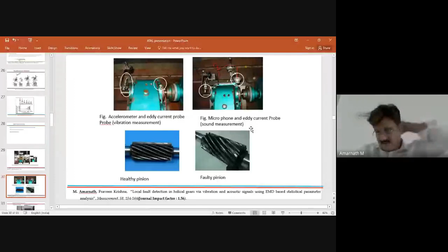So this is a zoomed view of the sensors. The vibration sensor, the accelerometer, is mounted on the bearing housing. Then the displacement probe is also there on the shaft. For every rotation, one pulse will be there in the displacement signal. That particular pulse is considered to get the details of one rotation of the vibration signal. Then a microphone is also used in conjunction with vibration, because both vibration and sound go hand in hand. If noise is more, vibration is more. If noise is less, normally vibration is less. That is the concept of this condition monitoring technique.